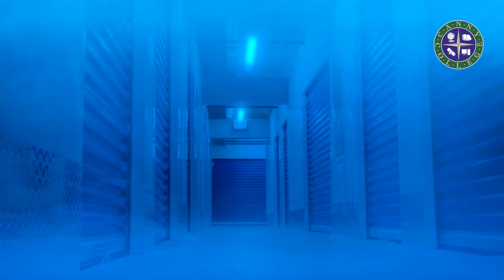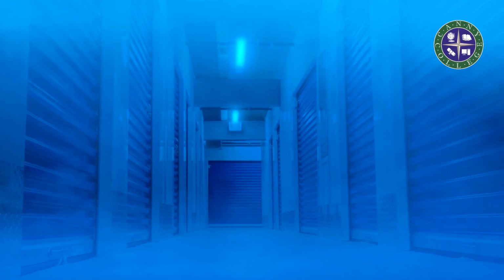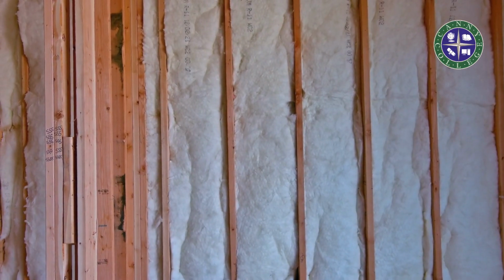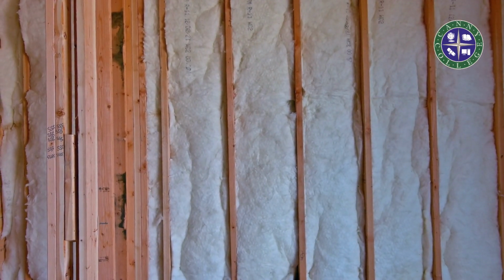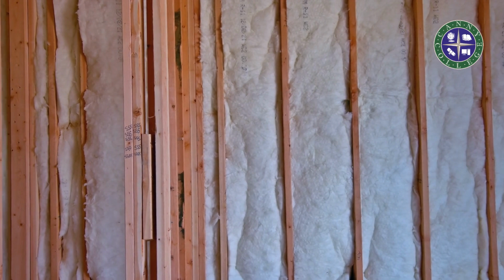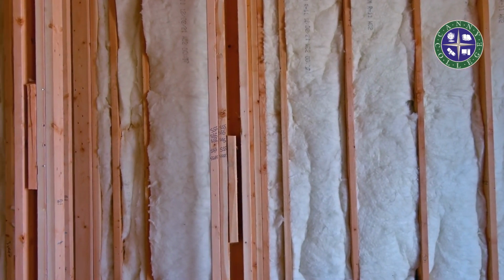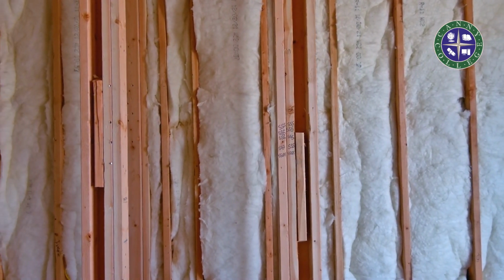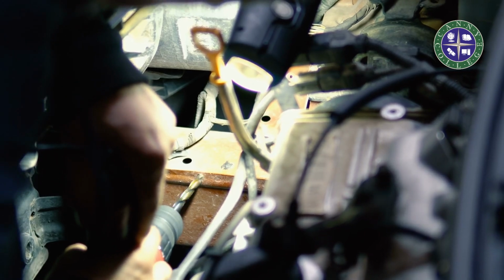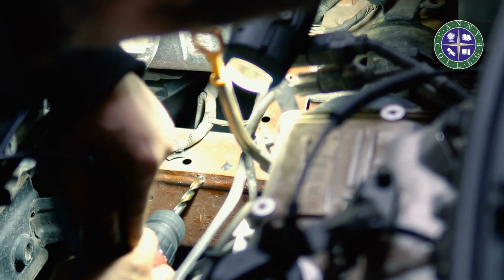2. Placing the vapor barrier on the inside, on the coldest side, could lead to condensation forming on the barrier itself, which can compromise its effectiveness and lead to moisture-related problems within the insulation in the freezer box. 3. Installing the vapor barrier on the outside, on the warmest side, helps to minimize the risk of moisture infiltration from the exterior into the insulation. This helps preserve the integrity and performance of the insulation over time.